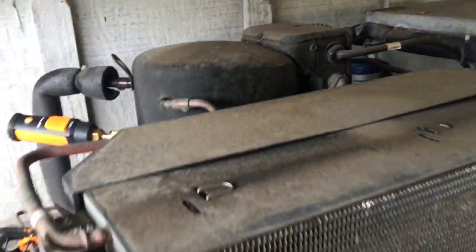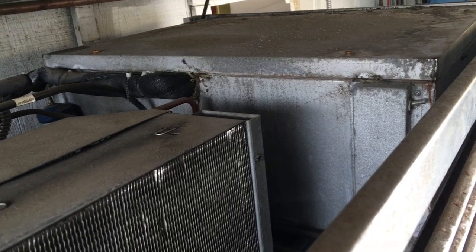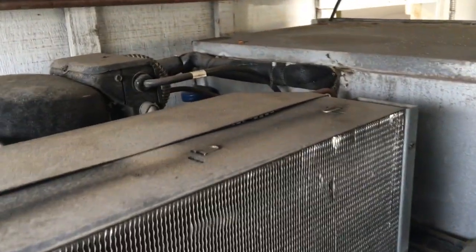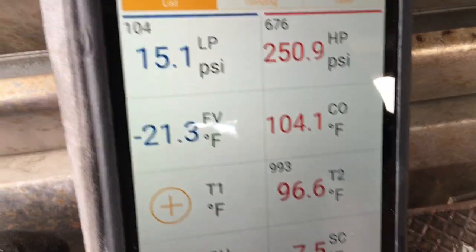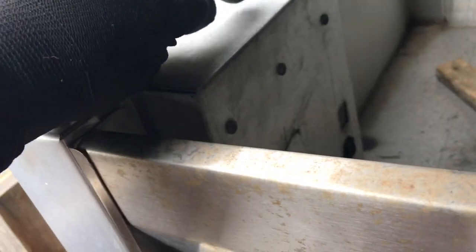So now we're in a quagmire. We are working on a fridge that now looks normal. Oil is clean, evaporator fans are working fine. Pressures look great for a freezer. We're at the mercy of an interface, a relay pack, a contactor, and some probes.